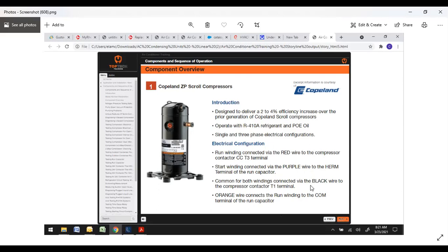So if you have a new unit or you're replacing a compressor, and all of a sudden you get locked rotor amps, obviously check your capacitor. But the next thing is go back and verify that your wiring is correct. Run is red, start is purple, common is black, and make sure your orange is going to the common side of your capacitor.